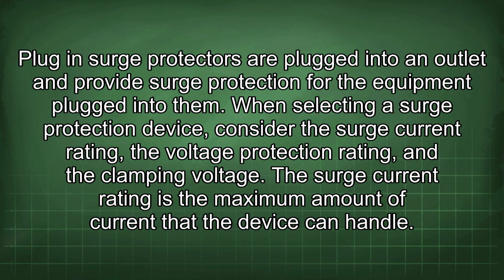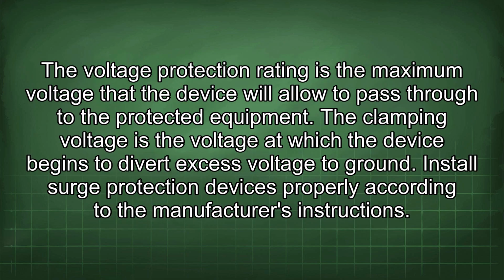When selecting a surge protection device, consider the surge current rating, the voltage protection rating, and the clamping voltage. The surge current rating is the maximum amount of current that the device can handle. The voltage protection rating is the maximum voltage that the device will allow to pass through to the protected equipment. The clamping voltage is the voltage at which the device begins to divert excess voltage to ground.